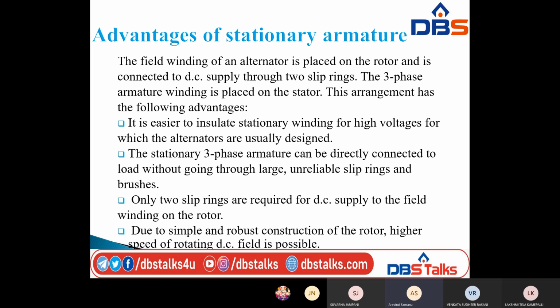This arrangement has the following advantages. First, it is easier to insulate a stationary winding for high voltages, for which alternators are usually designed. Again, the stationary three-phase armature winding can be directly connected to the load without going through large, unreliable slip rings and brushes.